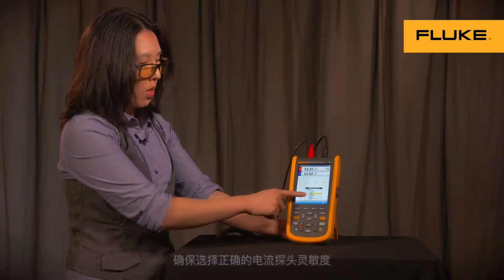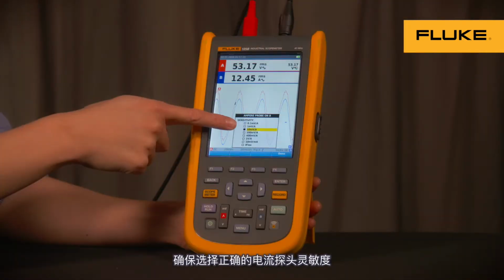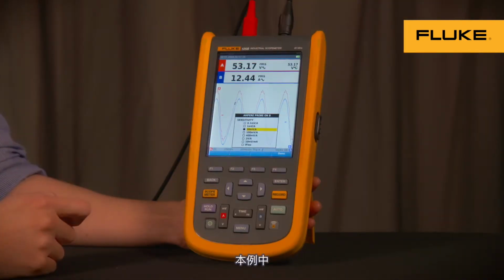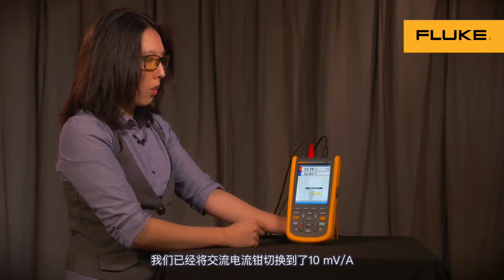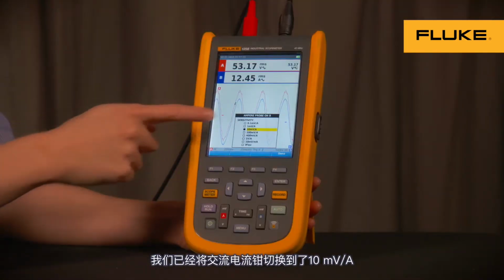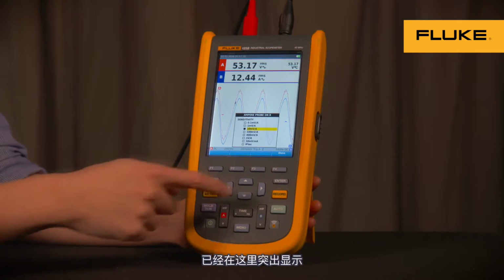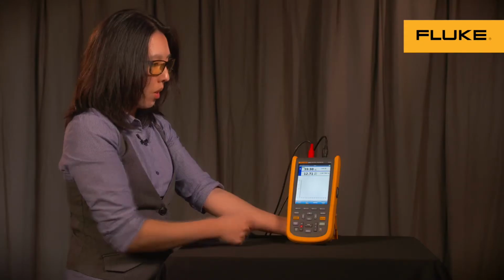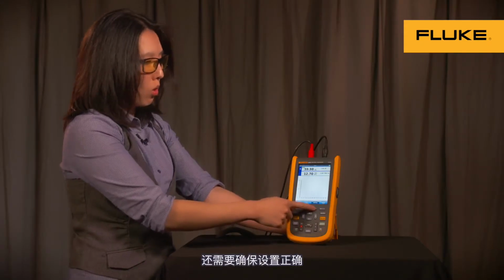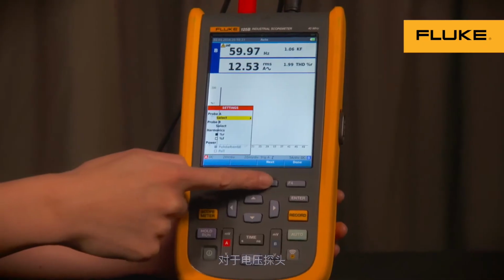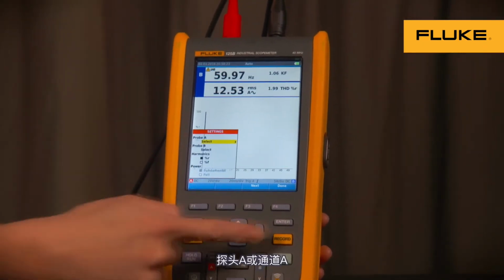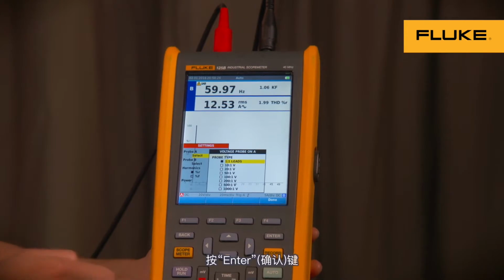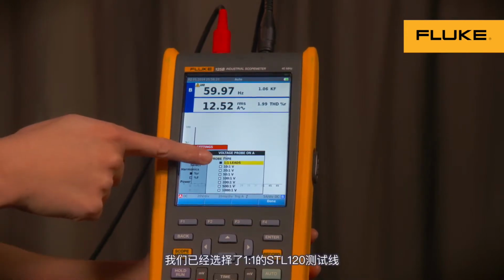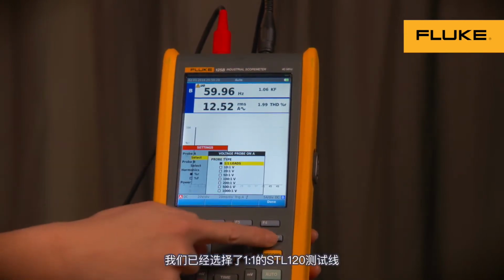For initial setup, make sure you select the right sensitivity for your probes. So in this example, we have the AC current clamp switched to 10 millivolts per amp, which is highlighted here already. Press the enter key. You also need to make sure your settings are right. Press F3 for your voltage probe, probe A or channel A. Press the enter key. In this case, we have the 1-to-1 test lead, which is the STL-120.